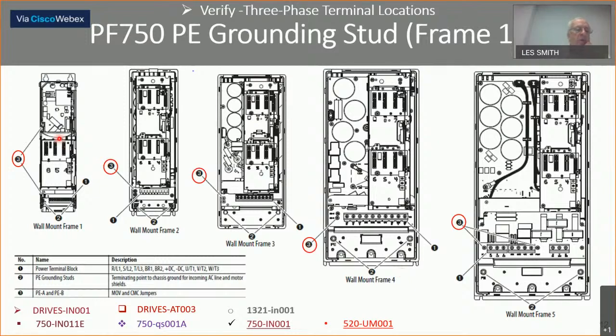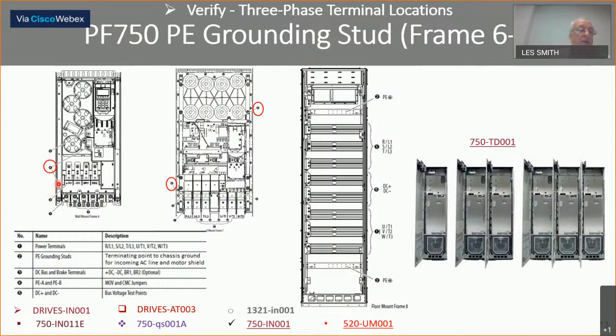Here's the frame 1. We won't be talking about that today. That's just a smaller drive for compact applications. This is a frame 2, and so right here, the 2 jumpers. It's a screw head that goes on top of a U-shaped jumper, and it shorts the 2 U's together, or 2 W's together. And same thing on frame 3 and frame 4. Now on frame 5, we separate them a little bit. Now we go up to frame 6 and 7, and look, we move this one down here and this one up here, very similar on the frame 7. That goes up to 400 horsepower.